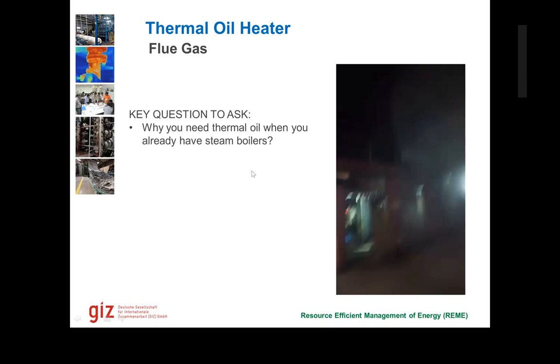The question is, why do we need thermal oil when we already have steam boilers? For the thermal oil heater, I think the reason is that in the factory there are some processes that need a high temperature. So with the available steam source, they cannot meet the demand. For example, we need up to 200 Celsius degrees. If we use the boiler, then the pressure will be very high. The boiler is around 8 to 10 atmospheres, so it cannot meet the requirement of a high temperature as the thermal oil heater supplies.